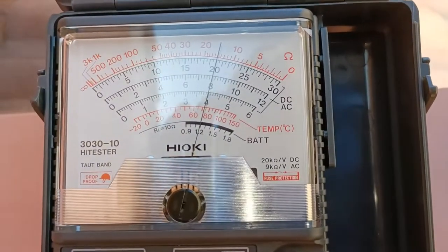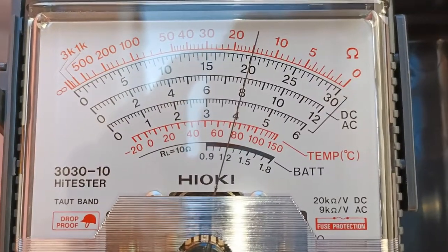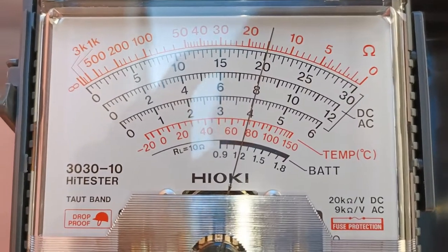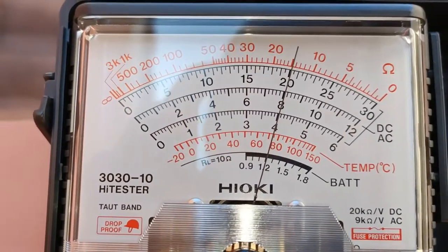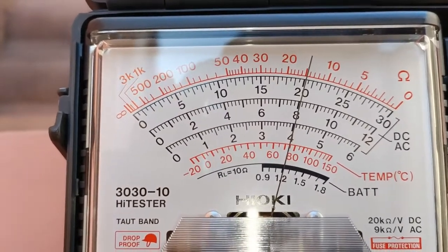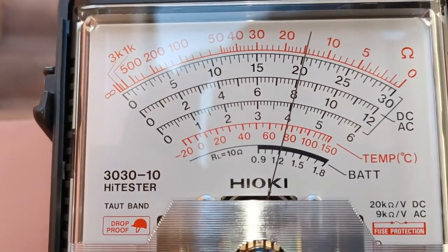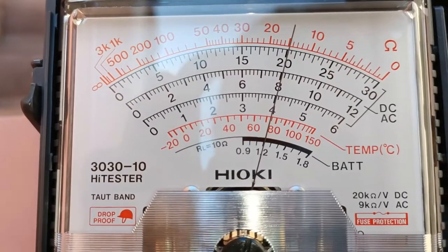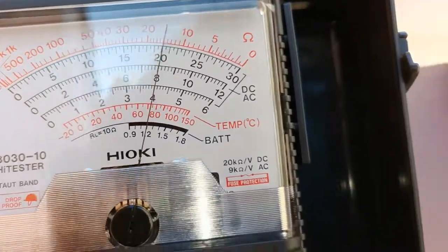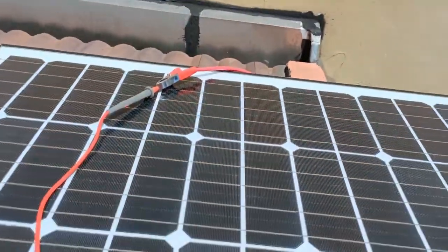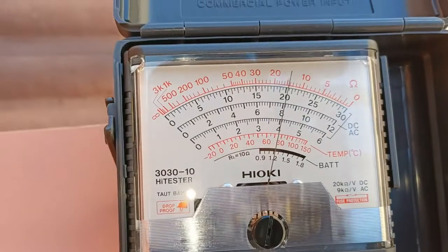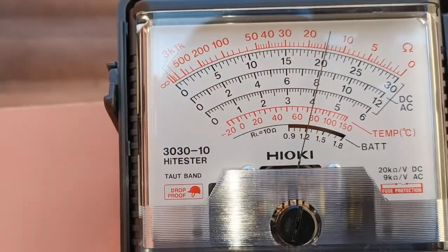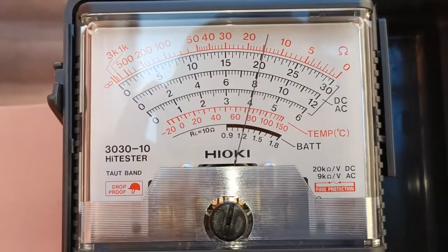I am getting reading of 20V DC. It depends on the position of the solar panel itself and the time of the day and the amount of sunlight that actually hits the solar cells. So a reading at this time, at this very moment of 20V DC at the terminals of this solar PV panel. That 20V DC reading is acceptable. The solar panel is therefore working as it should.